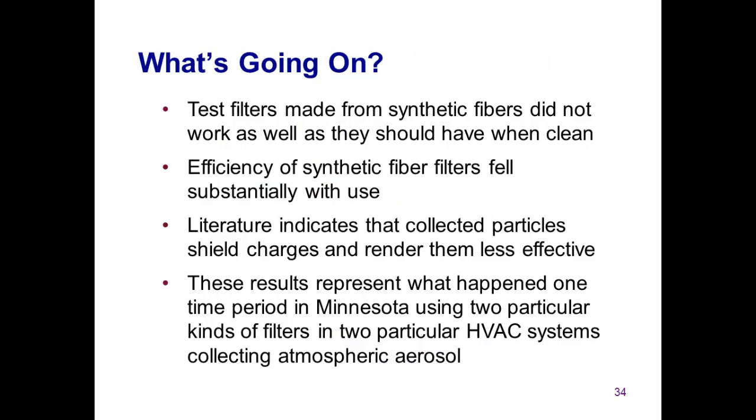So what went on during this test? First, the electret filters made from synthetic fibers did not work as well as they should have when clean, so we did not see the advantage that they should have when they are clean. Second, the synthetic fiber filters exhibited a substantial decrease in efficiency as they were used. The scientific literature indicates that it is likely that the collected particles shielded the permanent electrostatic charges on the filter fibers, making them less effective at helping to capture the incoming particles than they were when the filters were clean.